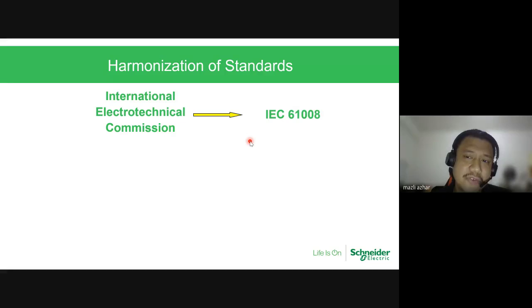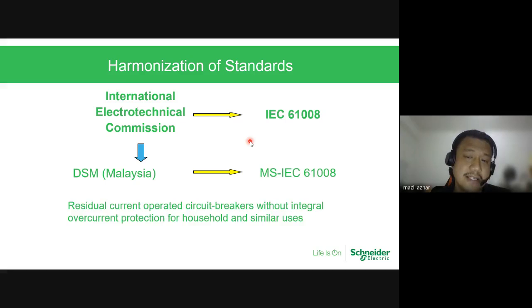So the standard we are referring to is IEC 61008. Under the Department of Standards Malaysia, it has been adopted as MS IEC 61008. So you can see here, this is a residual current operated circuit breaker without integral overcurrent protection. If you recall, the MCB is with overcurrent. So overcurrent protection is taken care of by the MCB. For leakage current, it is taken care of by the residual current device.